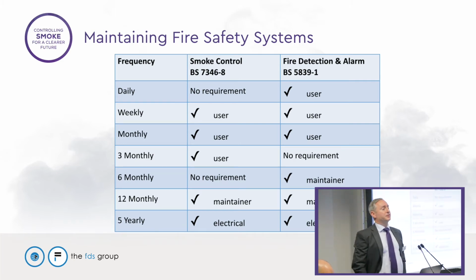However, what you often find on some large buildings is the fire alarm company will do 3 monthly visits on large sites, and what they do is they cut up the site into small chunks, and they do 25% of the building every visit. So 4 visits a year achieve a complete cover. At 6 monthly intervals, again, there's no requirement for smoke control other than ensuring the system is working correctly under the previous 3 monthly, weekly tests. But for fire detection systems, you are supposed to do more. You're supposed to do checks on detectors, make sure the panels are working correctly.